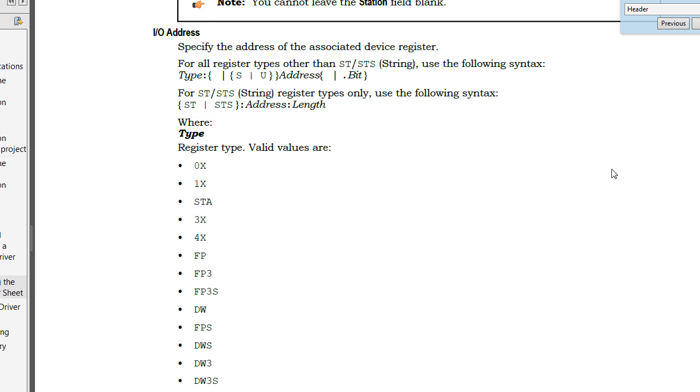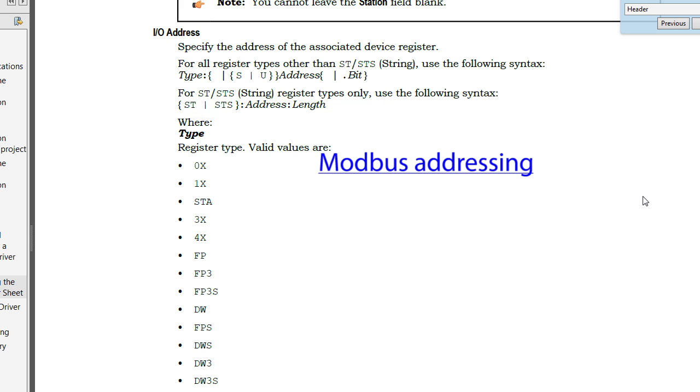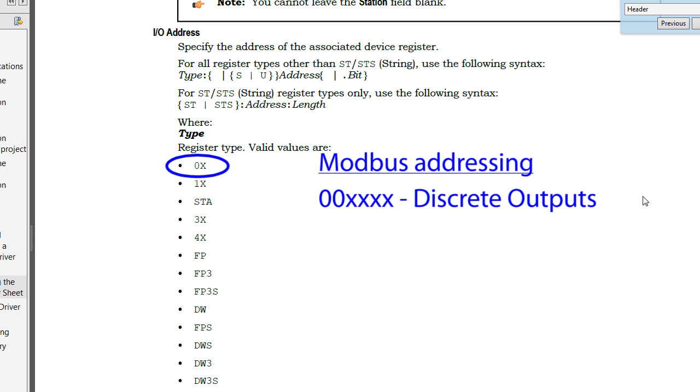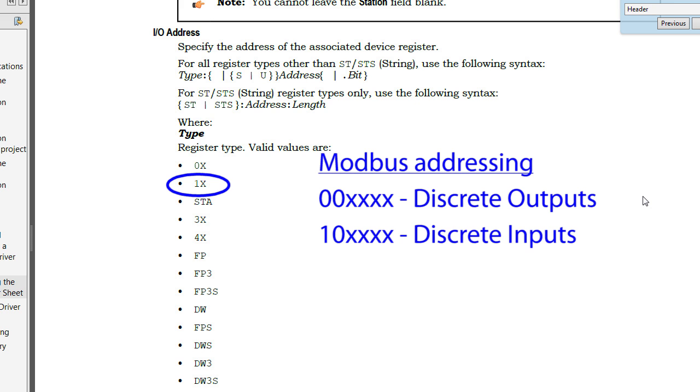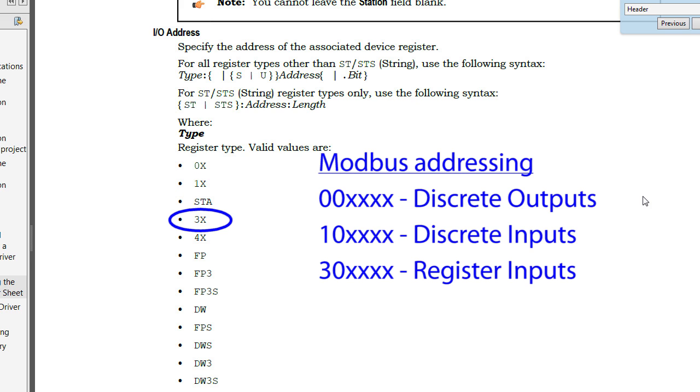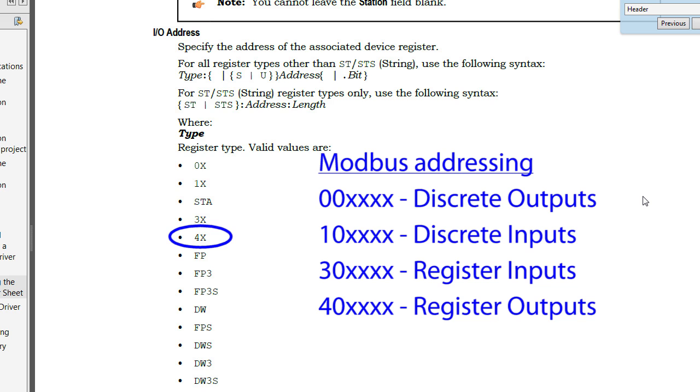This is a list of all the types this driver supports. In Modbus you usually deal with four types of registers: the 0,000 addresses are for discrete output coils, the 10,000 addresses are for discrete inputs, 30,000 addresses are for analog inputs or word inputs, and 40,000 addresses are for analog outputs or word outputs.